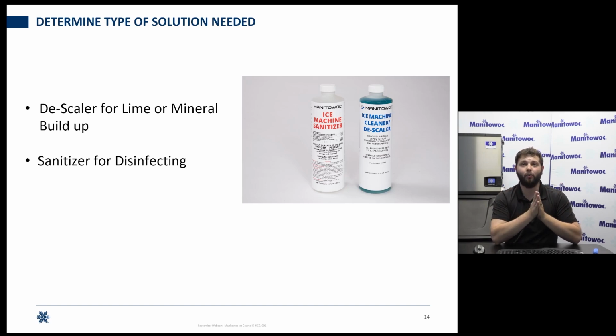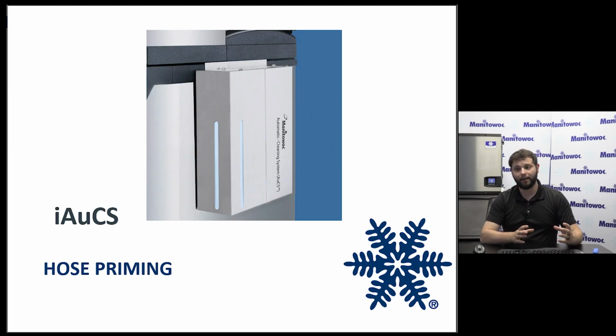Now we need to figure out what kind of chemical we're going to put in this. So we have two options. We have a descaler or we have a sanitizer. Now I will say, depending on what you choose, more than likely you will go with the sanitizer. If you have harder water, you see that the ice machine is getting scaled up a lot quicker, then you might want to go with the descaler. But otherwise, go with the sanitizer. That'll do good for you. Okay, so we have our bottle hooked up. It's inside the box. We can close everything up.